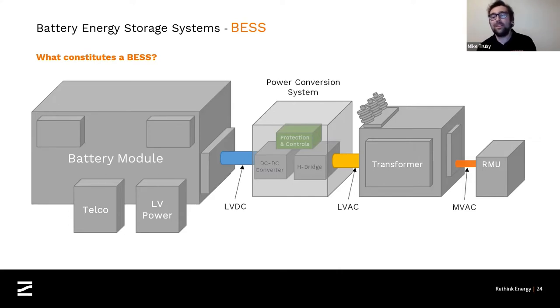And the LVAC current that we're getting out will typically be in the region of 400 to 900 volts AC. Again, it depends on the system and some other system limitations, including the current carrying capacity of that system. And that will then connect into a module transformer. As I mentioned, the module transformer is there basically to transform that LVAC current into an MV current. That is basically to minimize our losses around the plant, because as voltage goes up, current goes down, and therefore your resistive losses in the system go down as well.